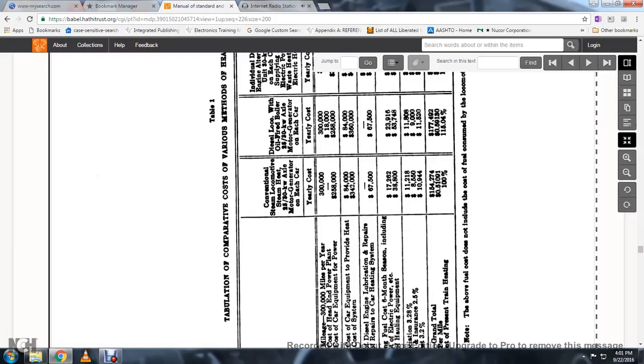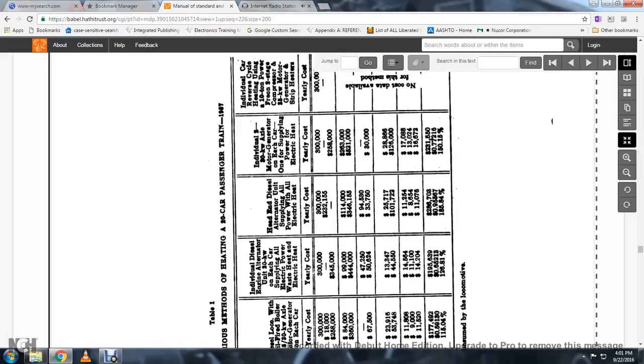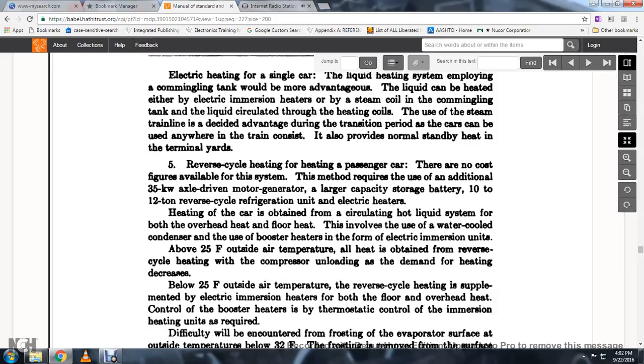This shows the tabulation and comparison of the various methods of heating a 20-car passenger train. Electrical heating for a single car using a liquid heating system with commingling tank has advantages in that the liquid can be heated by electrical immersion heater or by steam coil; the use of the steam train line coupling is a decided advantage during the transitional period as the cars can be used anywhere in the train consist, and provides standby heat in terminal yards. Reverse cycle heating requires the use of an additional 35-kilowatt axle-driven motor generator, a large-capacity storage battery, a 10 to 12 ton reverse cycle refrigeration unit, and electrical car heaters.